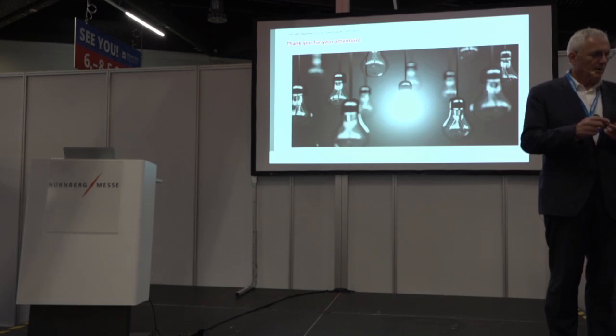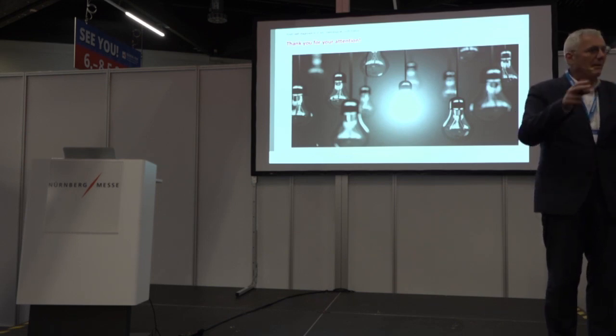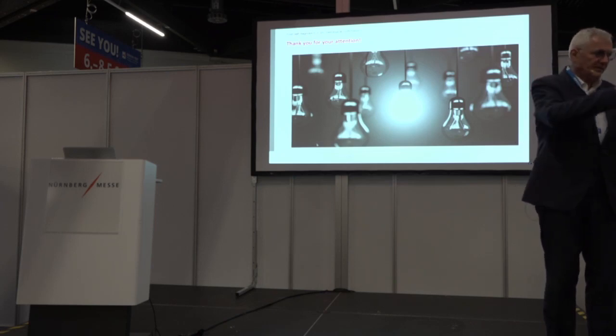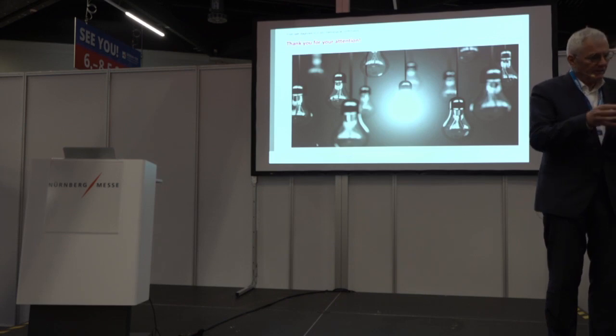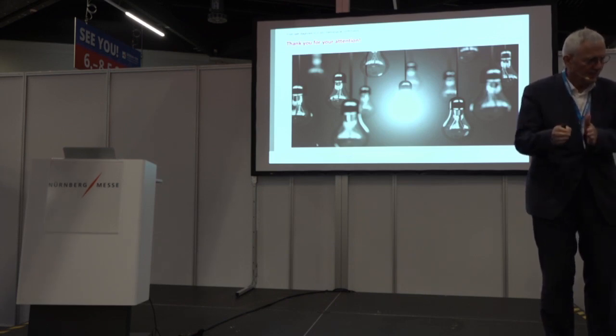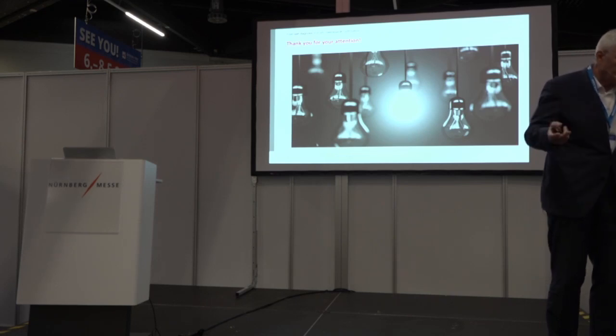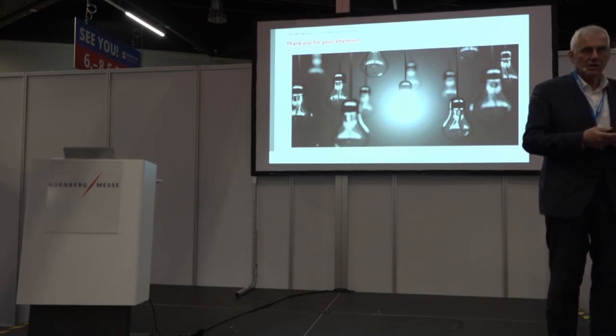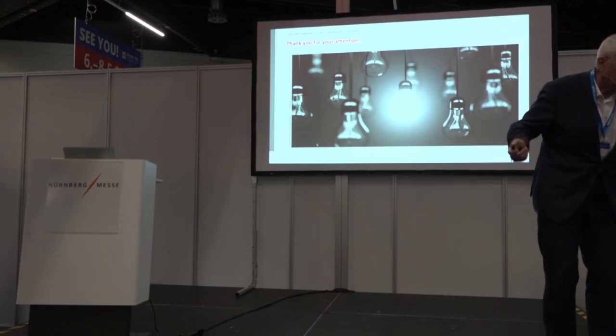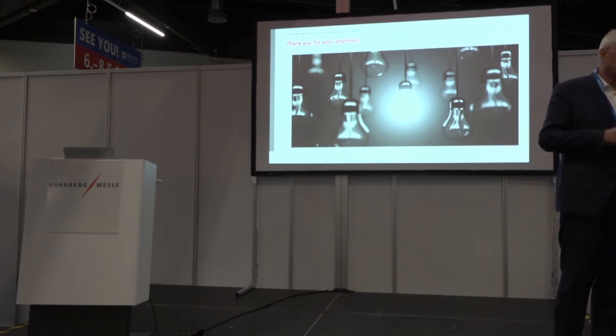They have 2 types of sensor application. One application is process control, and the other is safety. Safety against explosion: they measure the absence or the existence of certain gases, and if these sensors fail, you have a real problem, so they are very critical. Normally they have a map: this sensor has this criticality, that sensor that criticality. From this they define the number of calibrations you have to do. When it's very critical, maybe they calibrate every 3 months. When it's not so critical, maybe just water supply, they calibrate every 3 years. They think very much in criticality dimensions.